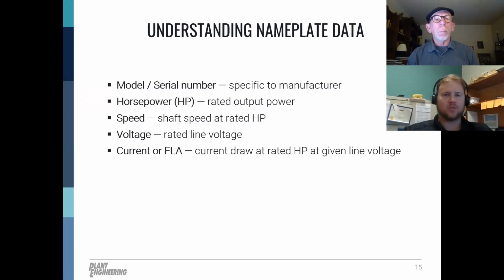So here are a few of the parameters that we talked about with motor nameplates. Some of these are involved in sizing the motor for the application and also matching the motor to the incoming power requirements. These include the horsepower, speed, voltage, and current. And then, as I alluded to a few minutes ago, each motor should have a specific model number. And then the manufacturer will likely give a serial number that designates it from all of its other products. One thing you will see with motors, they may have a model number, and then they may also have a catalog number. So something to keep in mind, and it's kind of interchangeable. Some manufacturers refer to catalog number instead of model number. But if you had a motor that you were looking to replace, along with these specs, you may be ordering based on catalog number and not necessarily model number.